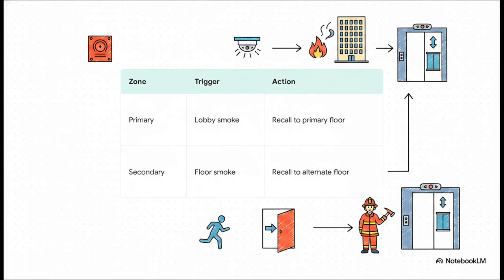Finally, fire protection. It's no longer just about laying out basic sprinklers. It's a highly complex, multidisciplinary interface. We have to rigorously program cross-system logic like elevator recall sequences. For example, if a primary smoke detector in an elevator lobby trips, the system instantly overrides the elevator, recalling it to a primary designated floor.